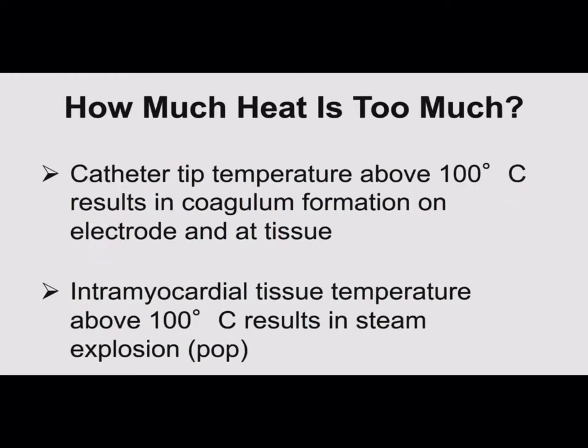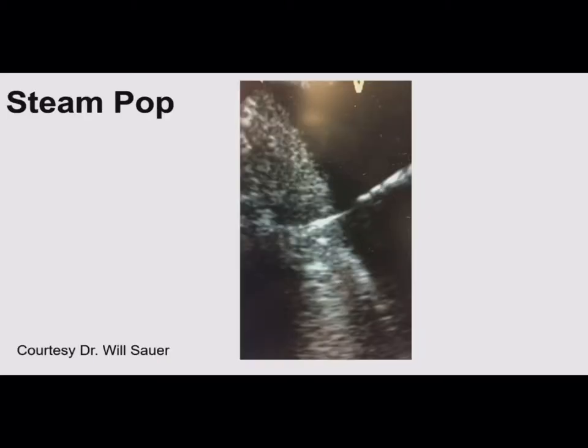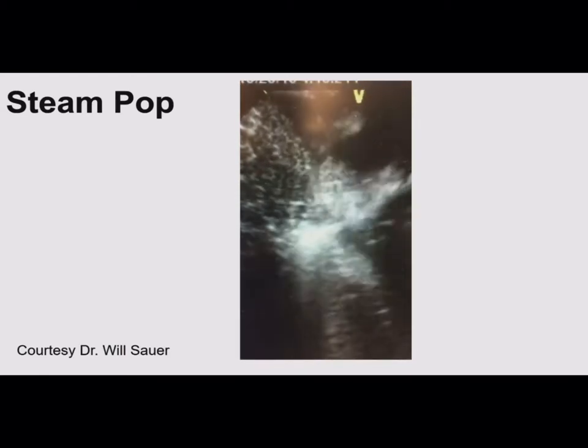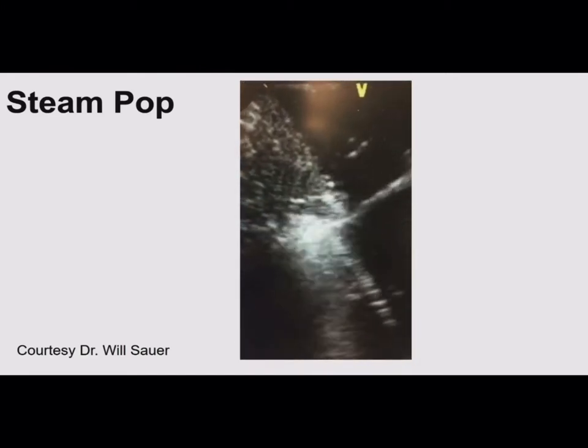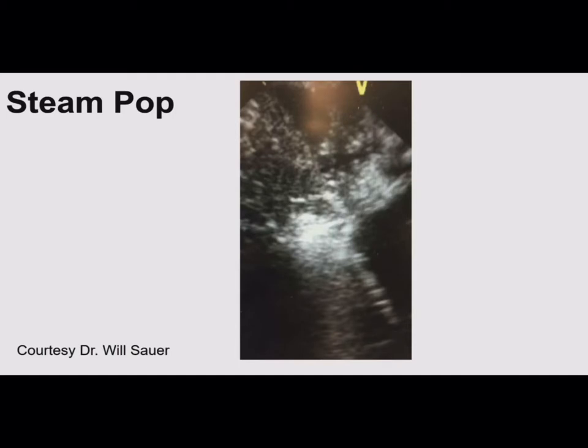The reason you don't want to heat above 100 degrees: one, you start to get coagulum or clot on the tip of the catheter, limiting your ability to heat the tissue. Second, above 100 degrees you're essentially boiling the water in the tissue, and if you do that inside the tissue, you get what's called a steam pop. This is in a swine left ventricle — what's happening is you're heating the water deep inside the endocardium, that water boils, there's nowhere to go, and that steam expanding results in a mini explosion.